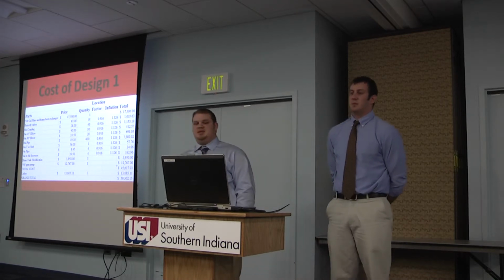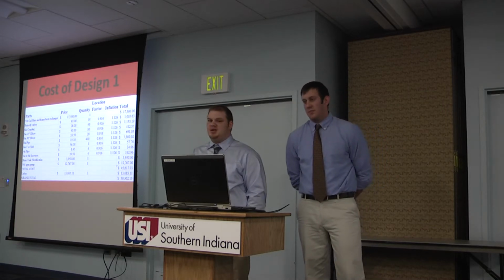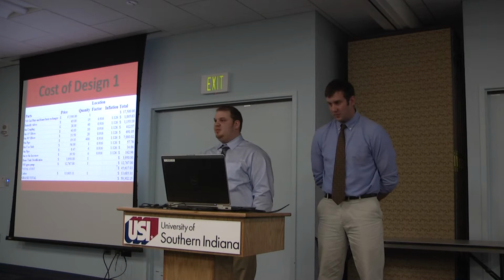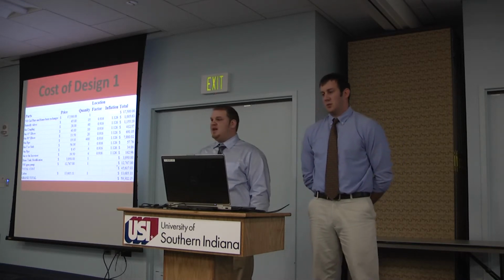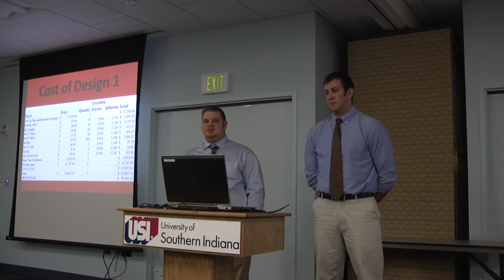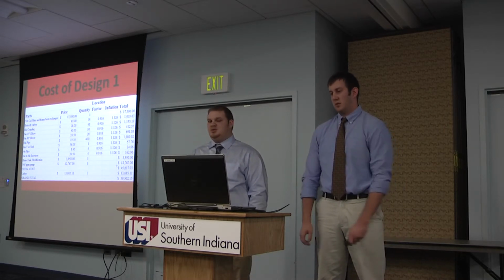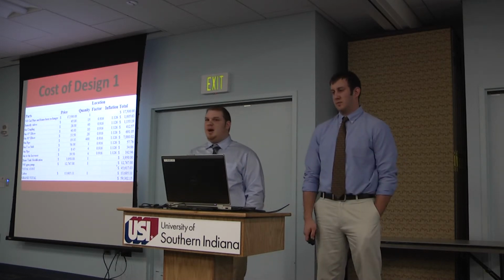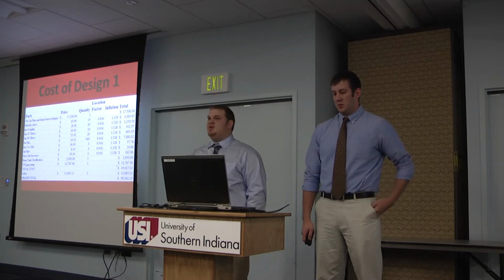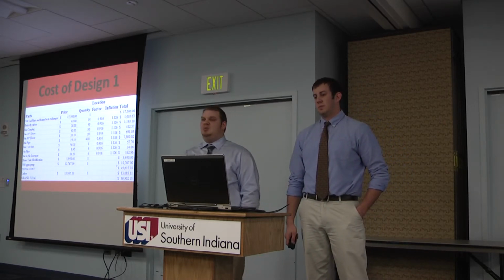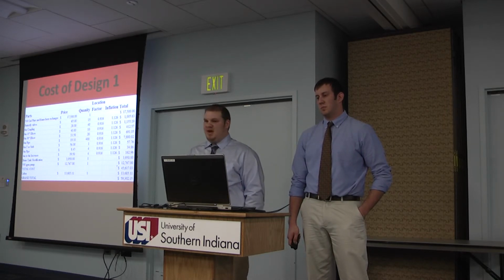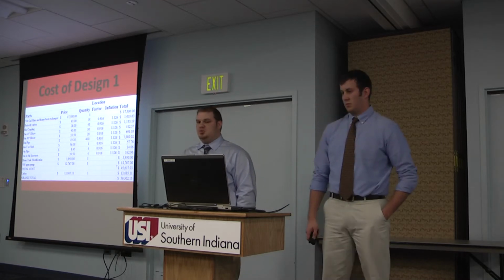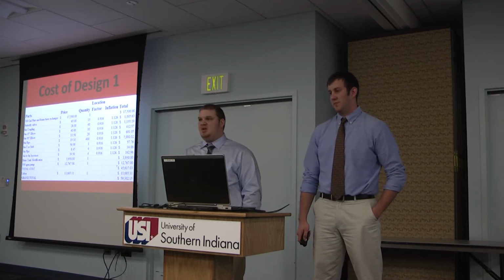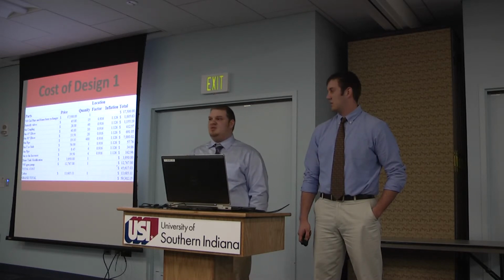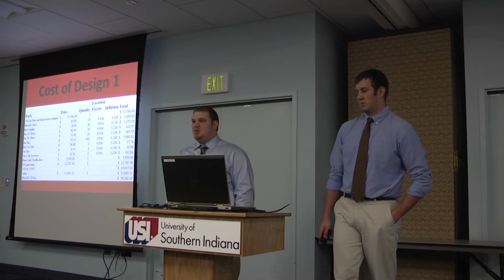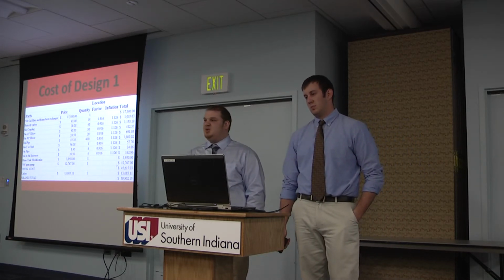On the cost of design one, as you can see, the grand total is just under $60,000. We've got our quotes from Alfa Laval for the plate and frame heat exchanger. The water pump came from Xylem Water Solutions, and the brine tank modifications came from WYN Industries, and then the pipe and the valves and all the couplings came from the 2007 Means Construction Guide. With that, we had to use a location factor for Evansville that took the national average across the board, and that's where the .916 comes from. And since the guide is from 2007, we had to apply an inflation factor to get it up to 2013 prices, which was 12.6%, and that got us to our total of just under $60,000.